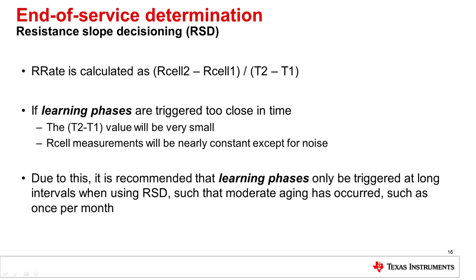How the device calculates the R rate is simple: it takes two R cell readings, computes R cell 2 minus R cell 1, and divides by the time stamp between those two readings. However, this brings up a limitation: if learning phases are triggered too close together in time, the T2 minus T1 value will be small, and since the device hasn't aged significantly, the R cell measurements will be very close — limited by noise and measurement inaccuracy. If you don't wait long enough for R cell values to change significantly between readings, you can get very erratic results. Because of this, when using RSD it is recommended to trigger learning phases at fairly long intervals — such as once every several weeks or once a month — so that moderate aging actually occurs between readings.